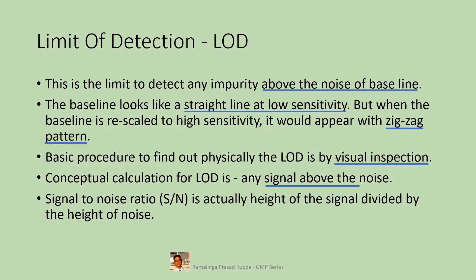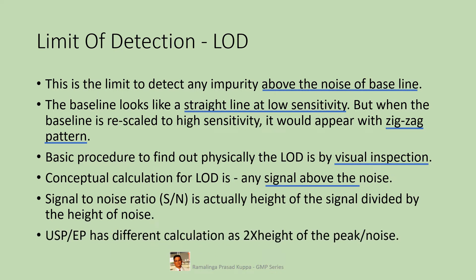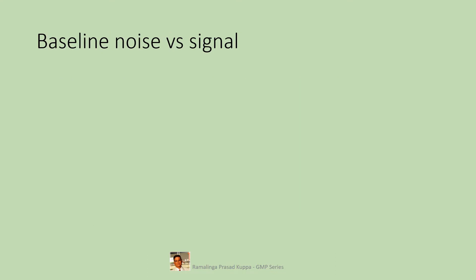Signal-to-noise ratio, S/N, is the height of the signal divided by the height of the noise. It is a simple mathematical expression — the ratio of signal and noise. You don't need to worry about how to calculate it; the software of your HPLC will do this automatically. Note that USP and EP have different calculations: two times the height of the peak divided by the noise. This gives double the result compared to the simple signal divided by noise method.